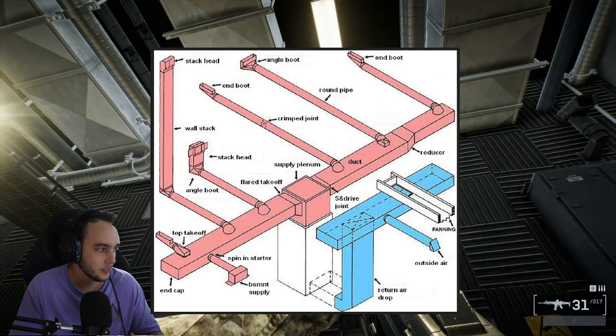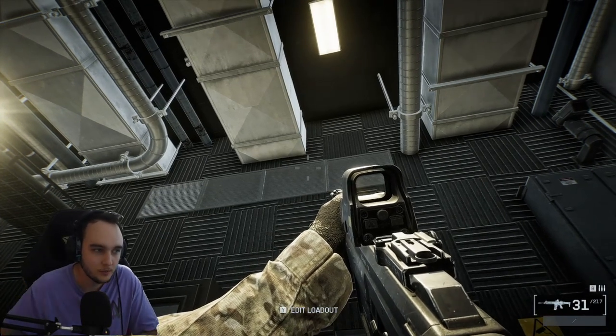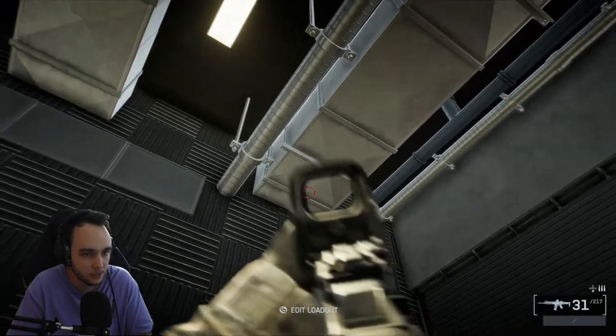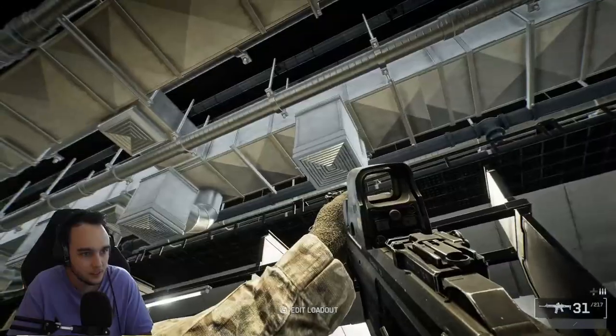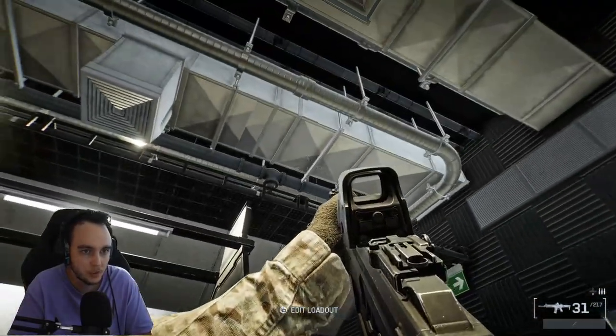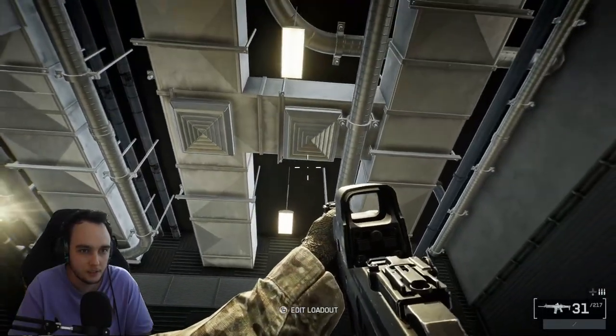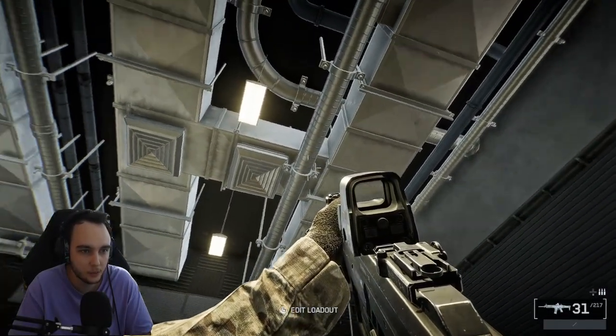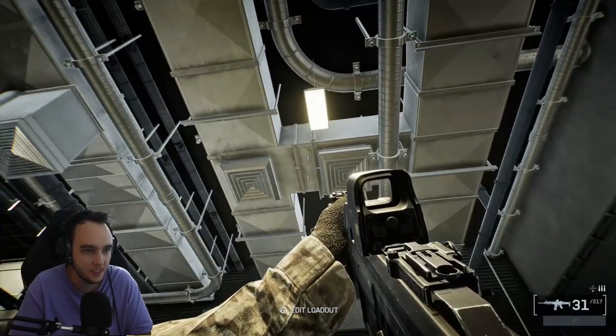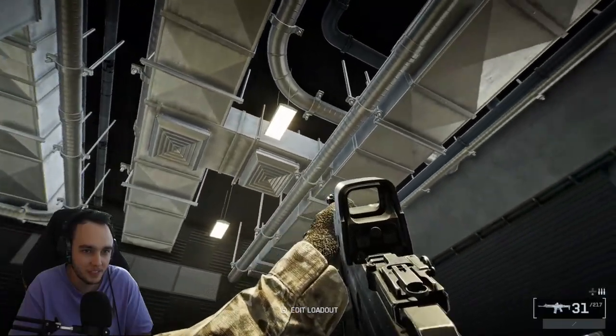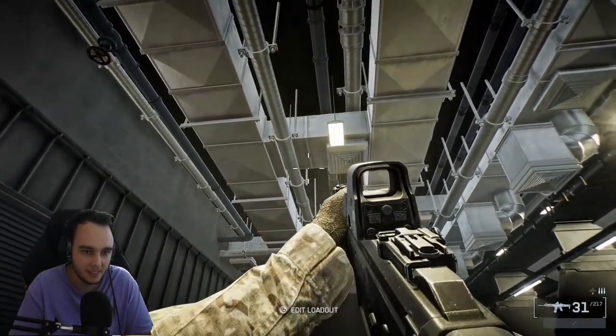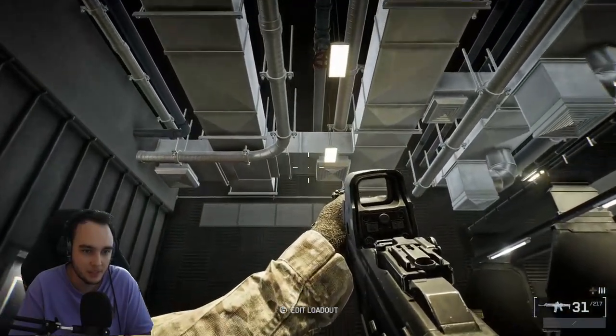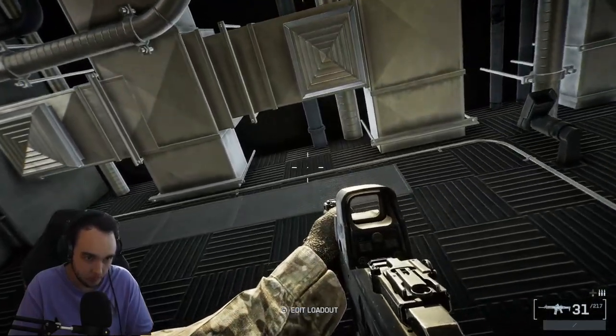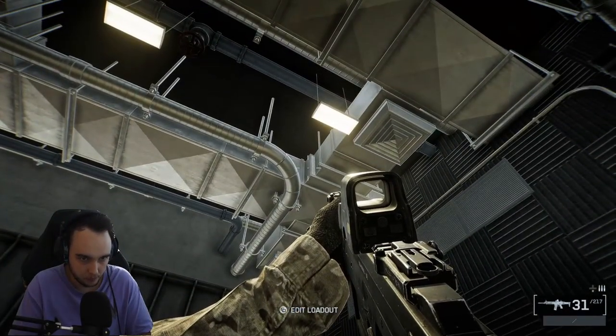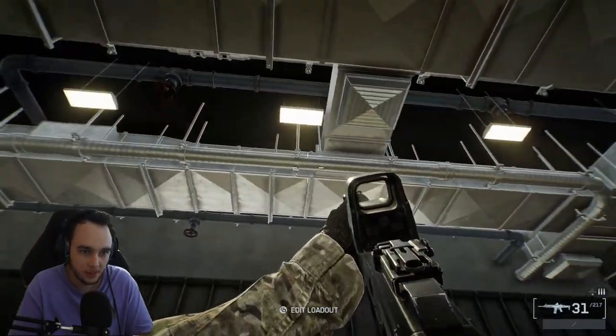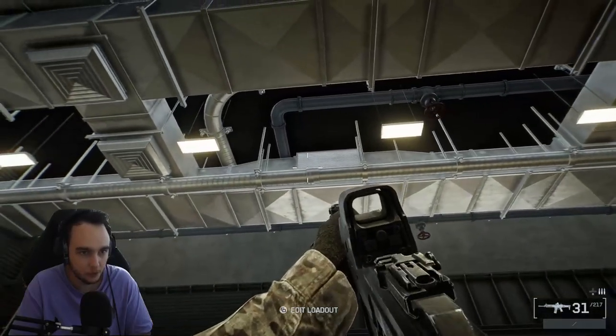So when I started looking at the systems in this firing range, I was like, oh, it's not so bad. We've got our return duct here, our supply duct here, and this kind of goes over the different booths, so maybe we'll call that the exhaust air. Looks pretty not good. Immediately we've got what looks like the return air and the supply air mixed into each other, connected at some point. And that just happens down the line, basically the whole way. And the kicker is, it looks like there are return grills on this branch in a few different places.